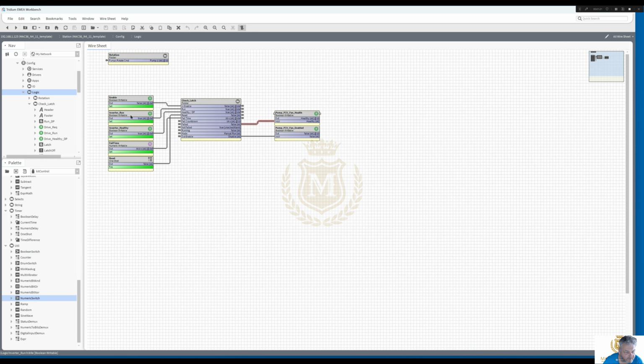That's because the inverter is actually giving a run signal. So if we've stopped it, that inverter should give it also a stop signal. So let's set that to stop. So we're now back to auto run. Inverter is healthy, we've got 30 seconds, no reset needed because there's no alarms, everything is okay.